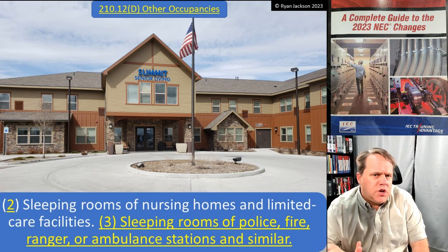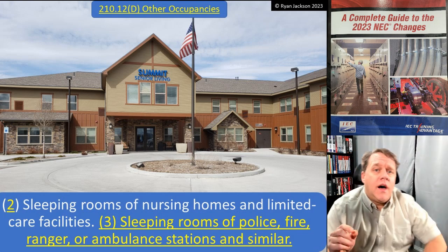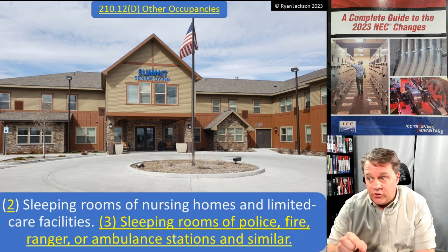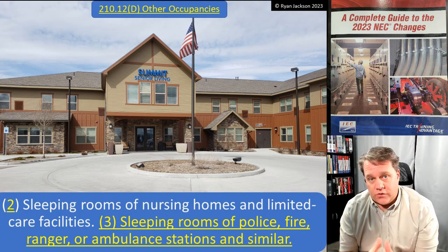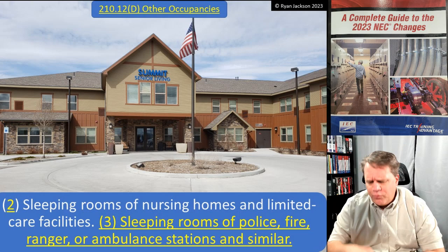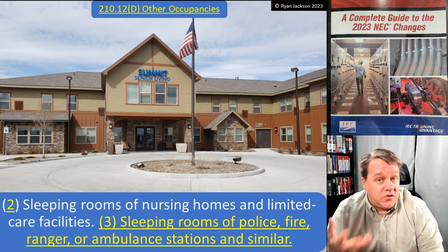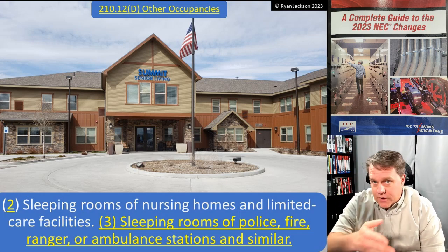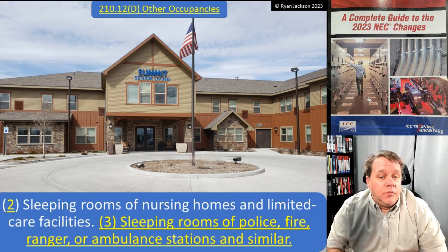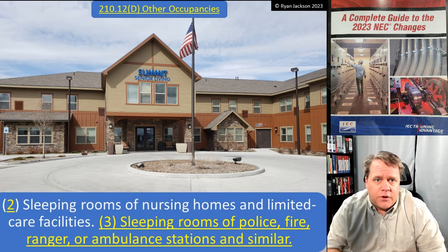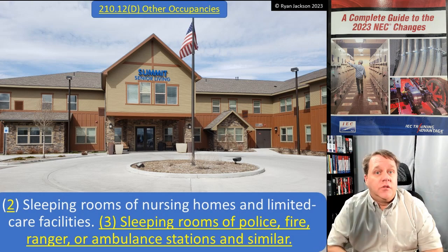This is a fairly predictable evolution when you look at AFCIs starting all the way back in 1999. We started putting AFCIs where people sleep — quite literally where they sleep, which was in dwelling unit bedrooms. Then we expanded to the rest of the dwelling unit and then to more locations. Then we added hotels and motels, then sleeping rooms in dormitory units, then nursing homes and limited care facilities — again, where people lay their heads. Now we're talking about sleeping rooms in police stations, fire stations, ranger stations, and ambulance stations.